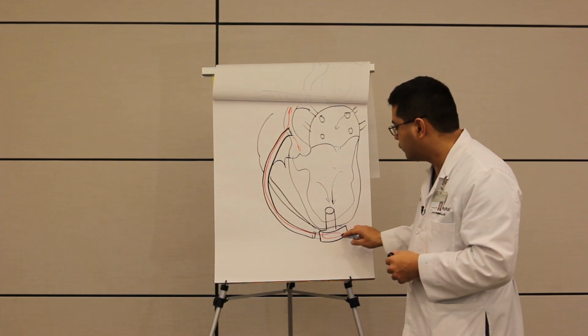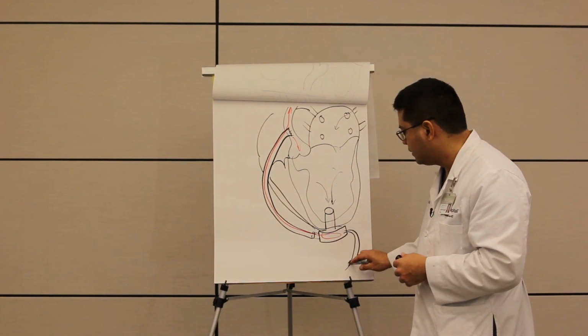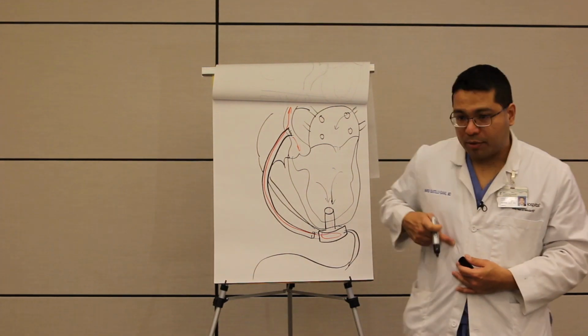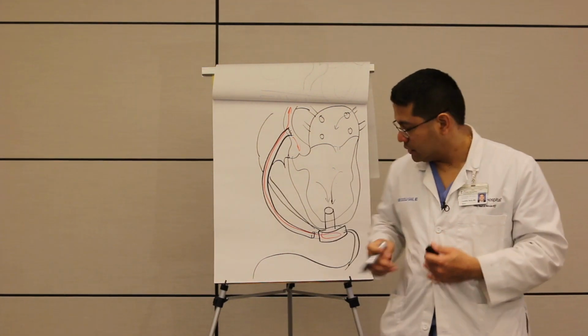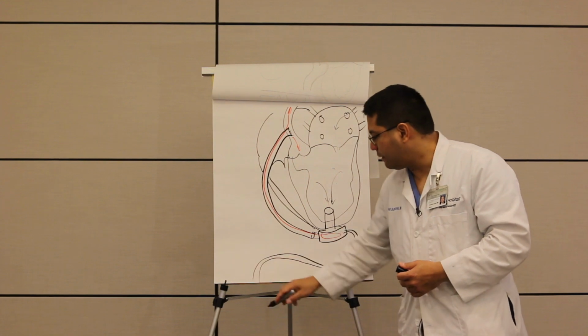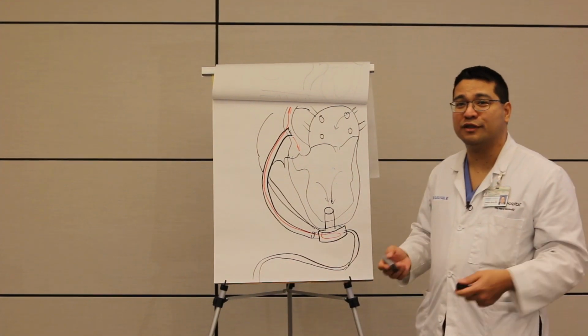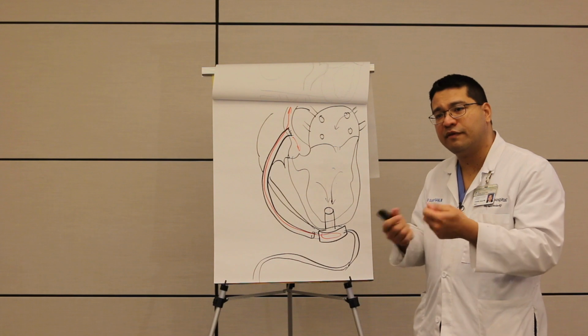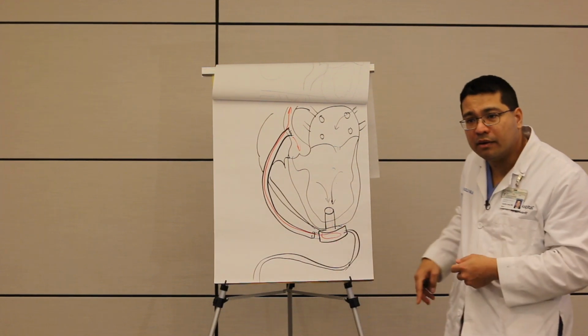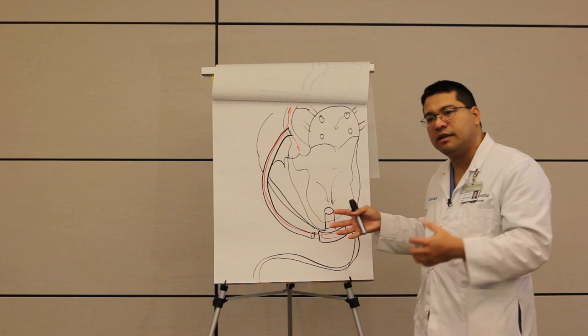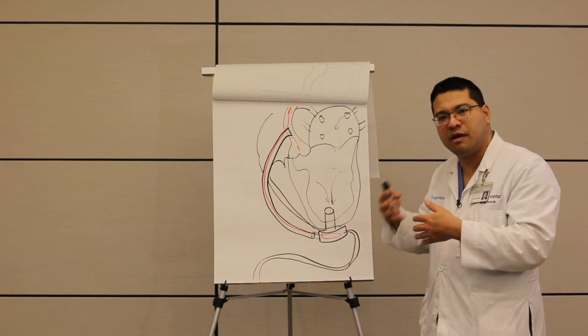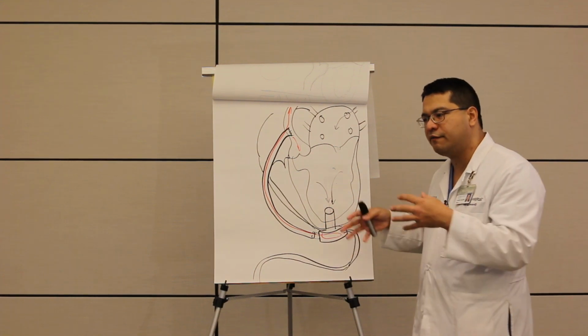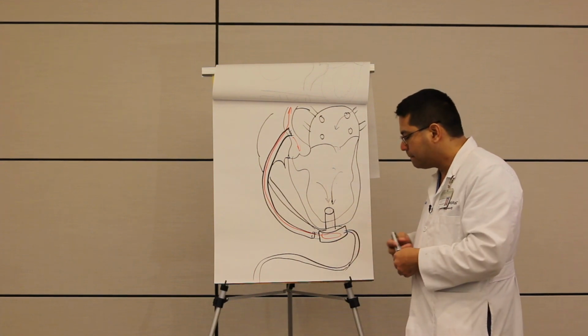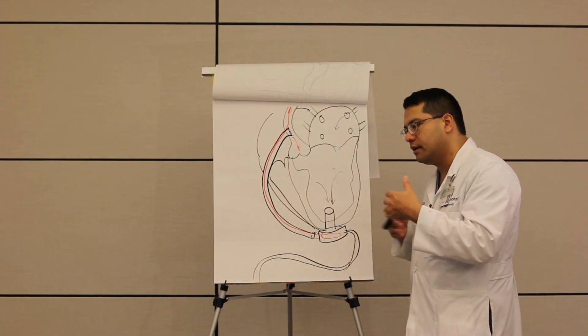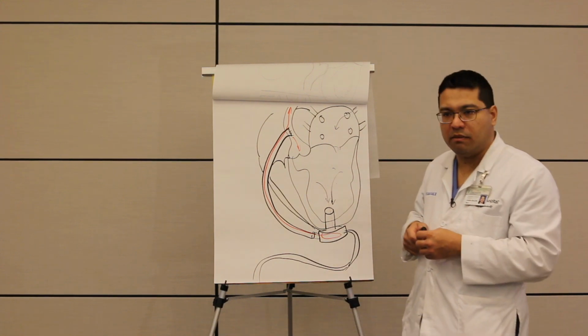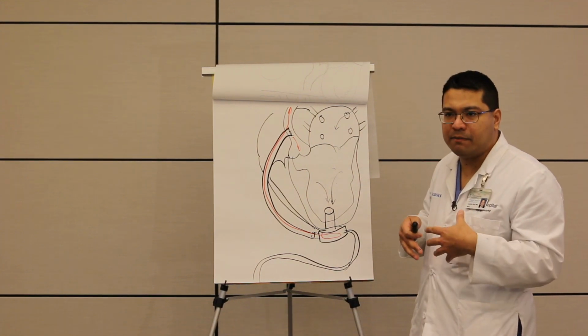So to control this pump, this has the drive line that exits usually the right upper quadrant, right under the rib cage. And that not only carries electricity to the pump, but also controls the speed and receives the information from the sensors in the pump about the thickness of the blood, the density of the blood, and how many RPMs are needed to propel the blood, all that. It's a very complex algorithm for any of the pumps. So this drive line is really the biggest problem in terms of being totally implantable.